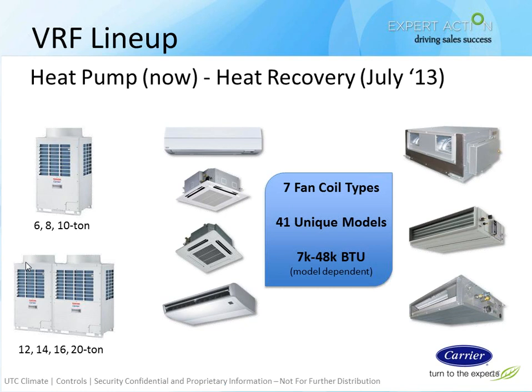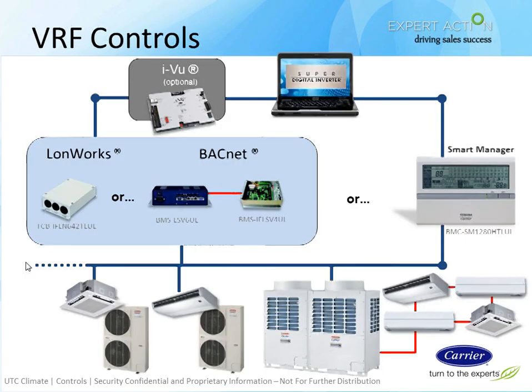We call it heat recovery because this can take heat from one area that's in the cooling mode and deliver that heat, if needed, to other areas of the building. So instead of rejecting the heat outside, we reject it inside and recover that heat and save energy at the same time. The Toshiba Carrier product also shares the advantage of being easily integrated into the Carrier controls platform in existence now that, of course, many contractors and, of course, TEC is familiar with.